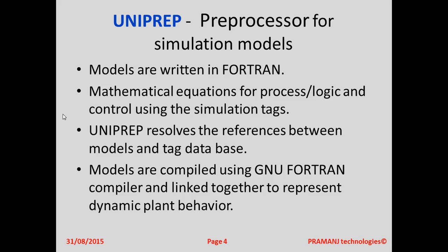The next tool is UniPrep, which is a preprocessor tool for the plant modeling software written in Fortran. The simulator is made up of a large number of such mathematical models for process, logic and control system to simulate the entire plant dynamic behavior and its control logic. The preprocessor resolves the tag references used in the individual models so that these models can communicate with each other in an integrated manner when compiled and linked together to represent dynamic plant behavior.